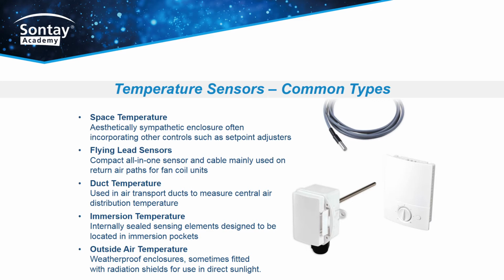Duct temperature, used in air transport ducts to measure central air distribution temperature. Immersion temperature, internally sealed sensing elements designed to be located in immersion pockets for fitting in areas like tanks or pipework. Outside air temperature, weatherproof enclosures, sometimes fitted with radiation shields, for use in direct sunlight. Choosing the correct sensor type and installing it properly is one of the most important parts of provisioning building control. Different sensor types are manufactured for different purposes, and it is important to select the correct device for the application. Temperature sensors come in many different formats and are not universally interchangeable.